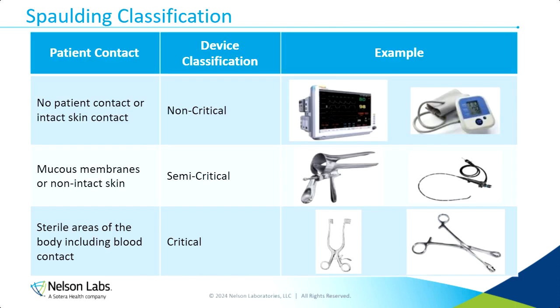So as we talk today, just keep in mind that reusable medical devices are classified into three categories using what's called the Spaulding classification. This is a way to categorize reusable medical devices based on how they interact with the patient and what the risk is to the patient, based on the intended use of the device. So devices that have no patient contact or may contact intact skin are classified as non-critical devices. These are the types of devices that I mentioned, those non-invasive devices. So items like blood pressure cuffs, carts, monitors, surgical lights, items that have low risk associated with them because they may not even contact the patient, or if they do, they'll contact intact skin. But they are still medical devices and still may be contaminated and as such need to be decontaminated between uses.